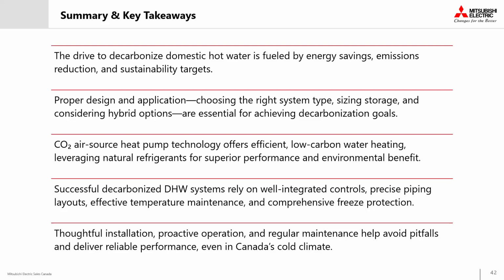So I would say that a lot of manufacturers offer strategies to combat the losses that you might see during defrost mode. Every manufacturer is going to have a different strategy to manage these things. One of the things that we use here at Mitsubishi Electric is that, prior to initiating a defrost sequence, the system will temporarily work with a boosted capacity. So we'll ramp up our pump, ramp up our compressor, and drive more heat into our loop prior to a defrost sequence, and try to balance out those losses as much as possible as we go into defrost. Like I said, every manufacturer has a different strategy, but that's one of the things that we do here at Mitsubishi Electric. Thank you so much.